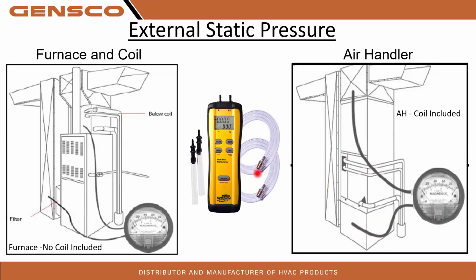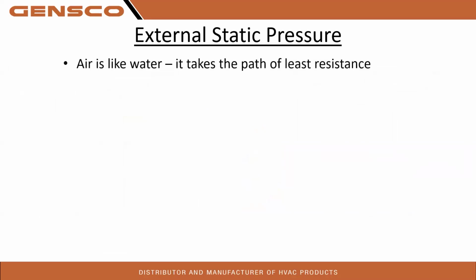There's a kit. We have that Fieldpiece. I do have that one. That's been a pretty good durable unit. You can use that for dialing in gas pressures for the gas valves. There is a kit with the static probes and the little magnetics. That's a great kit. That's a good meter. If you don't have one, get one. So, external static pressure.